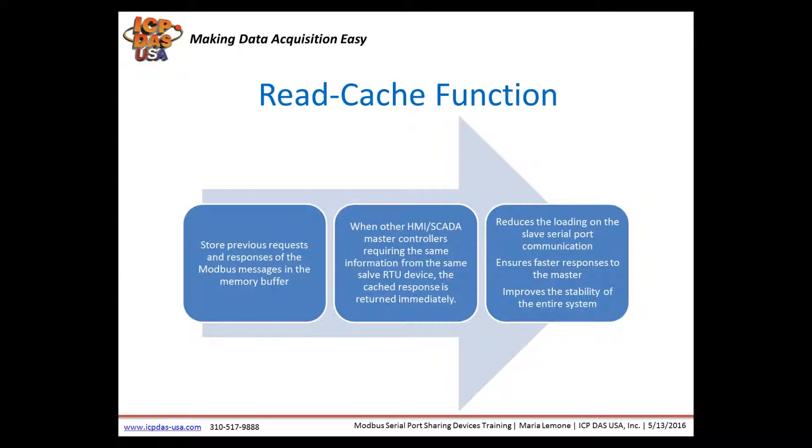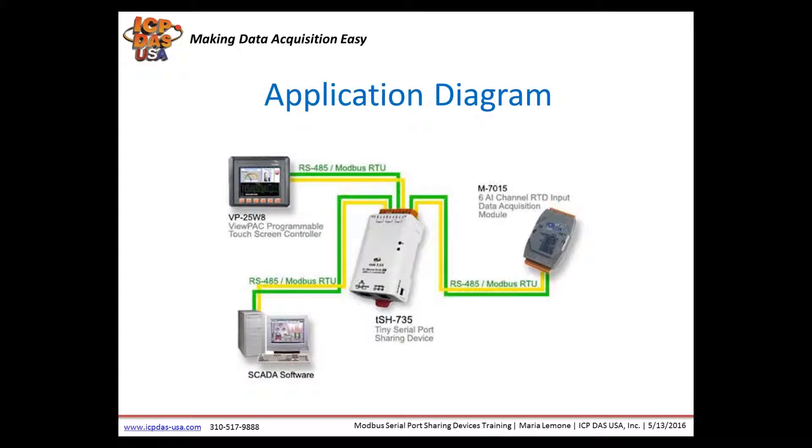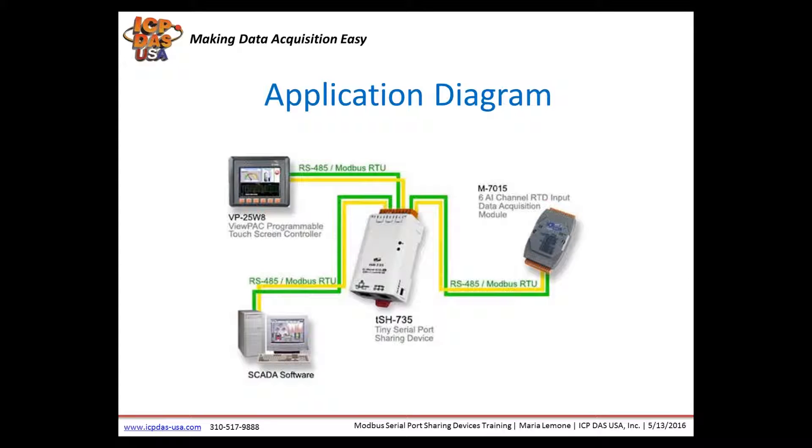The two masters sharing one slave feature allows two different masters to connect to different serial ports to share slave devices. The built-in cache function reduces the loading of serial communication on the slave port by removing duplicate queries when two master devices are requesting the same information. When two master devices request the same Modbus information, the built-in cache function removes duplicated requests to reduce the load of communication of the serial port.